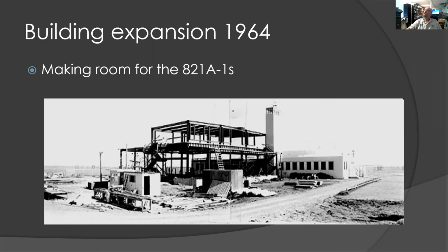They had to make room for that, so they built an extension onto the east side of the building, with 2 stories. The bottom floor housed the transmitters, the 3 821A1s as well as the 2 Continentals. The second story was for the cooling equipment for those transmitters. As you might imagine, 3 250 kilowatt transmitters, plus 2 50 kilowatt transmitters, produced a lot of waste heat, so we had to get rid of that. That's what the second floor housed.